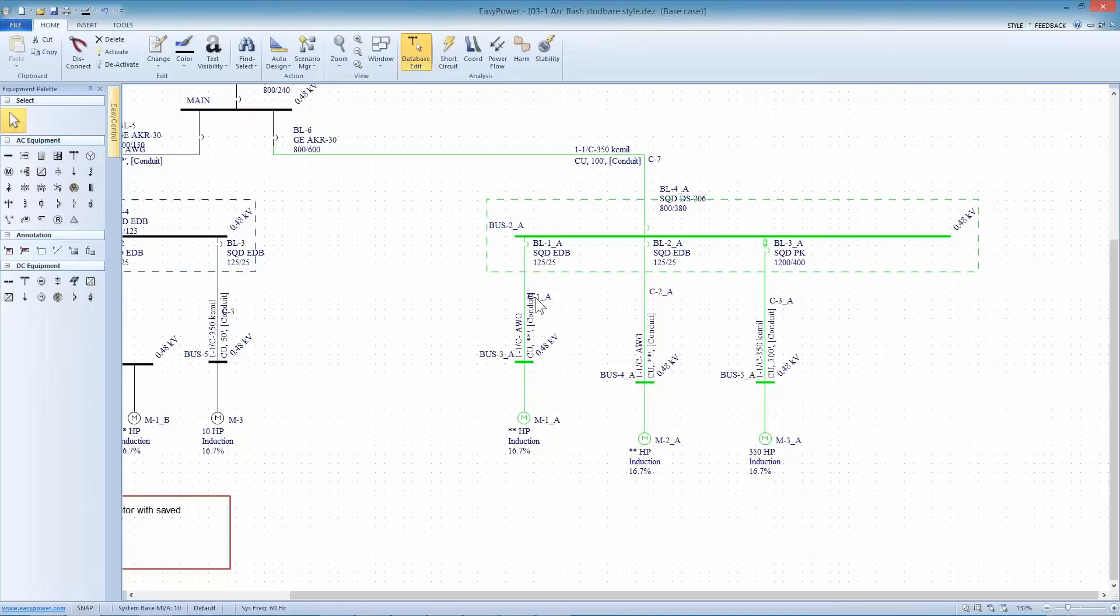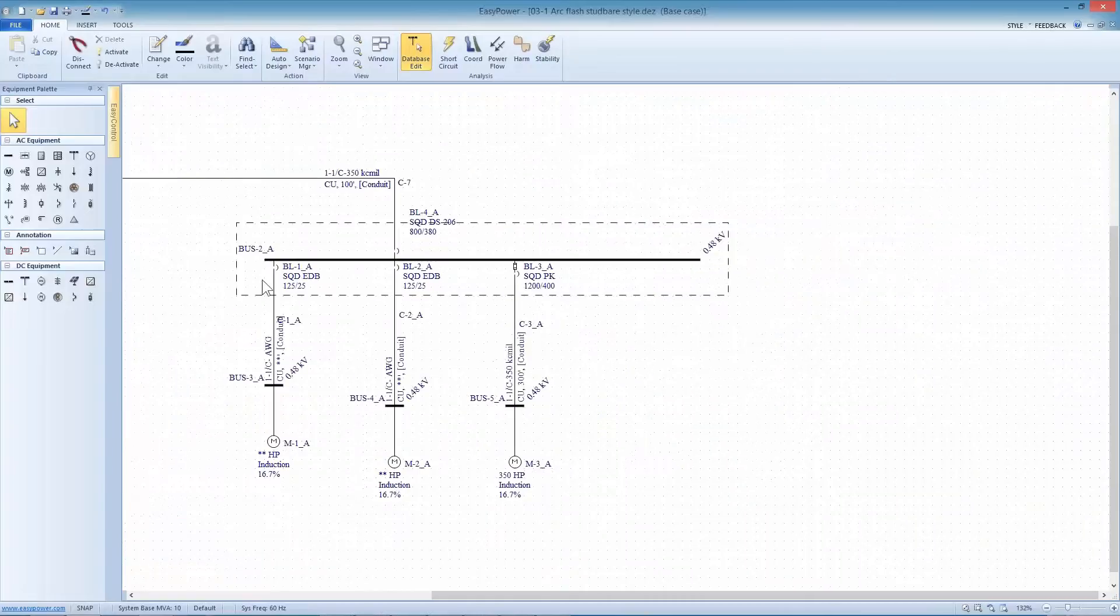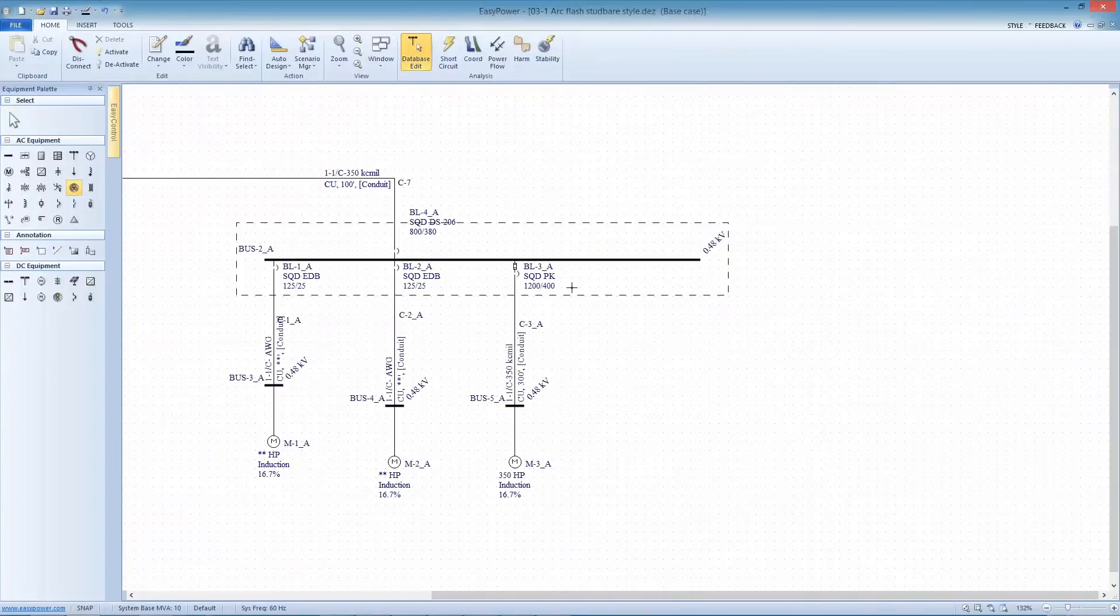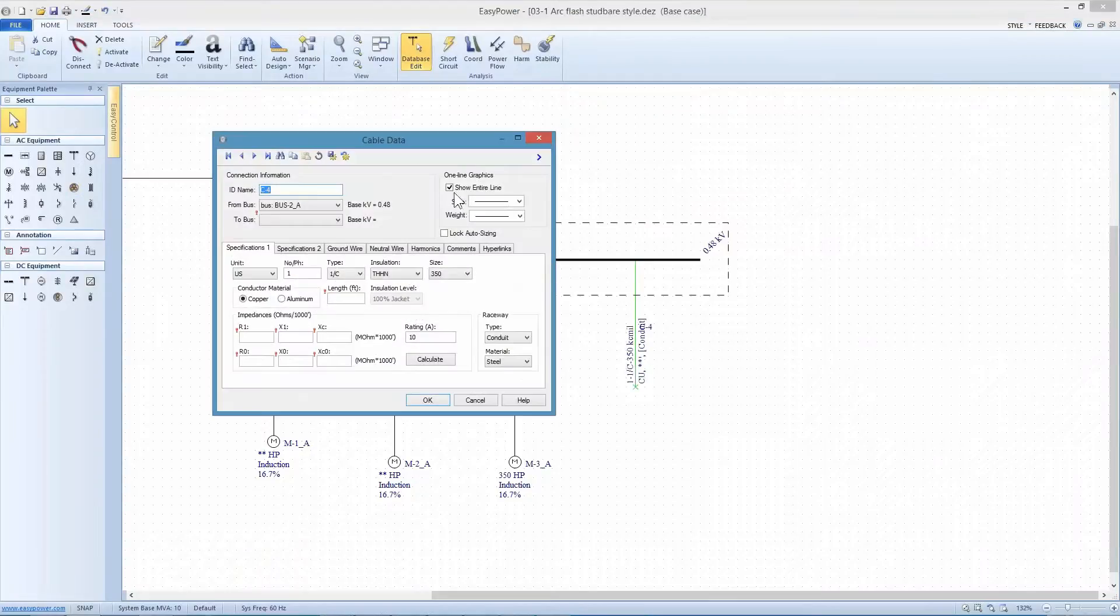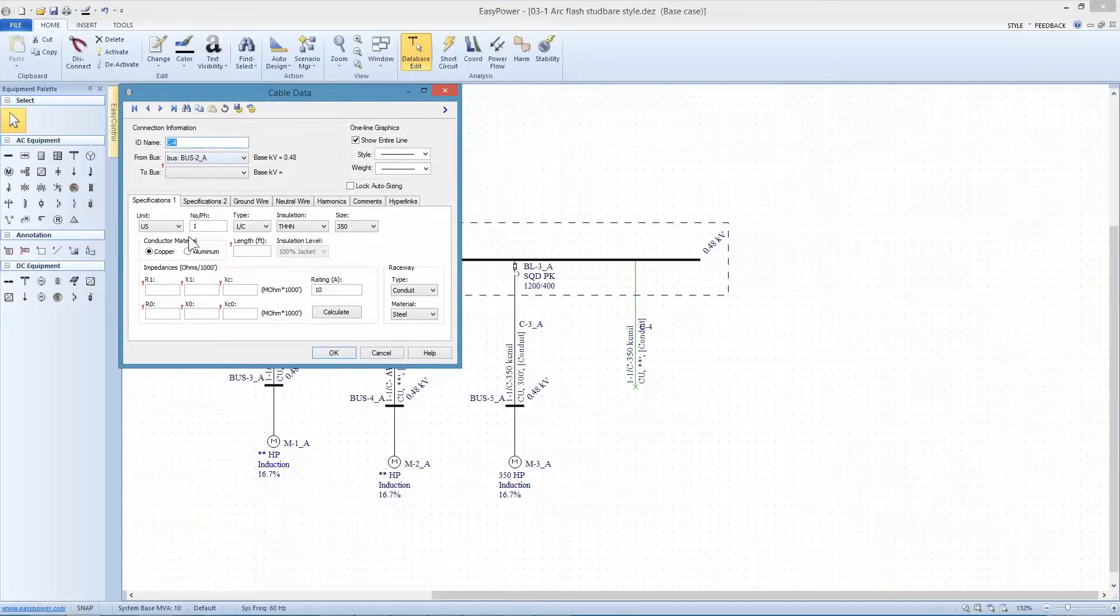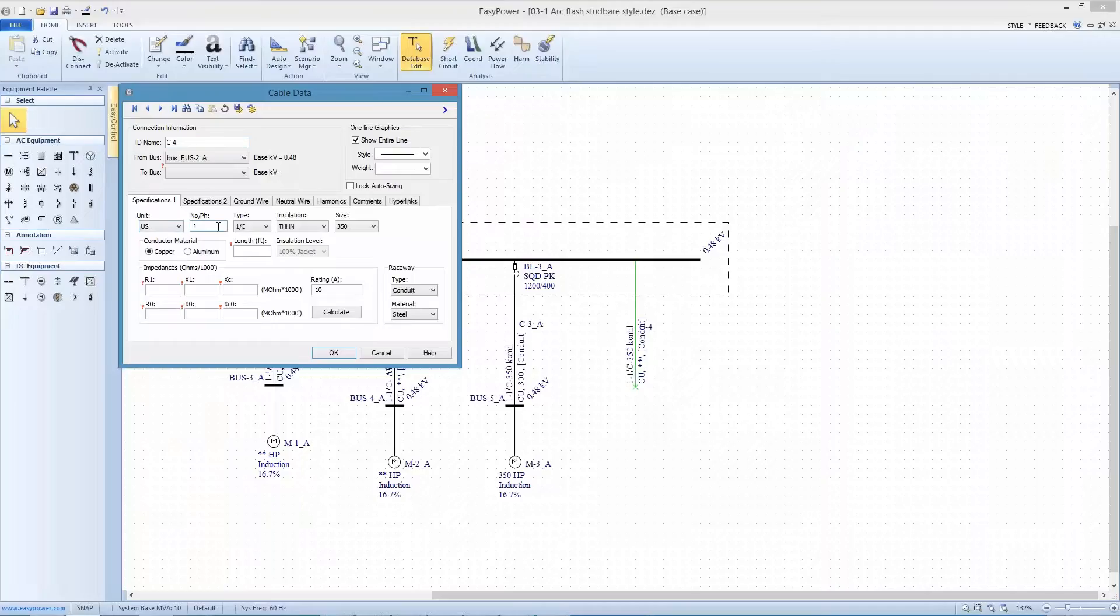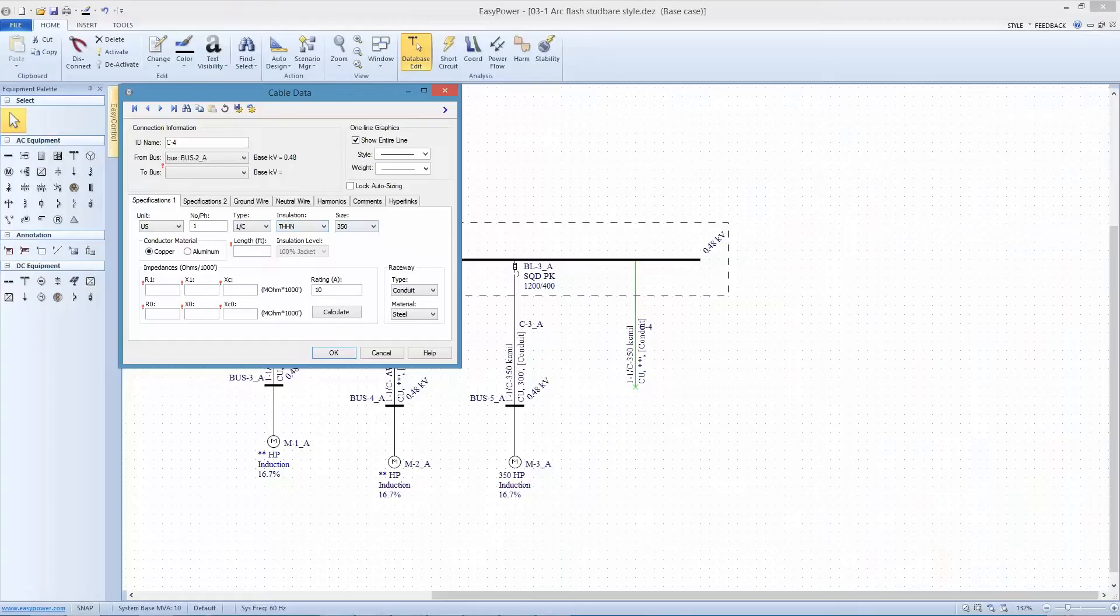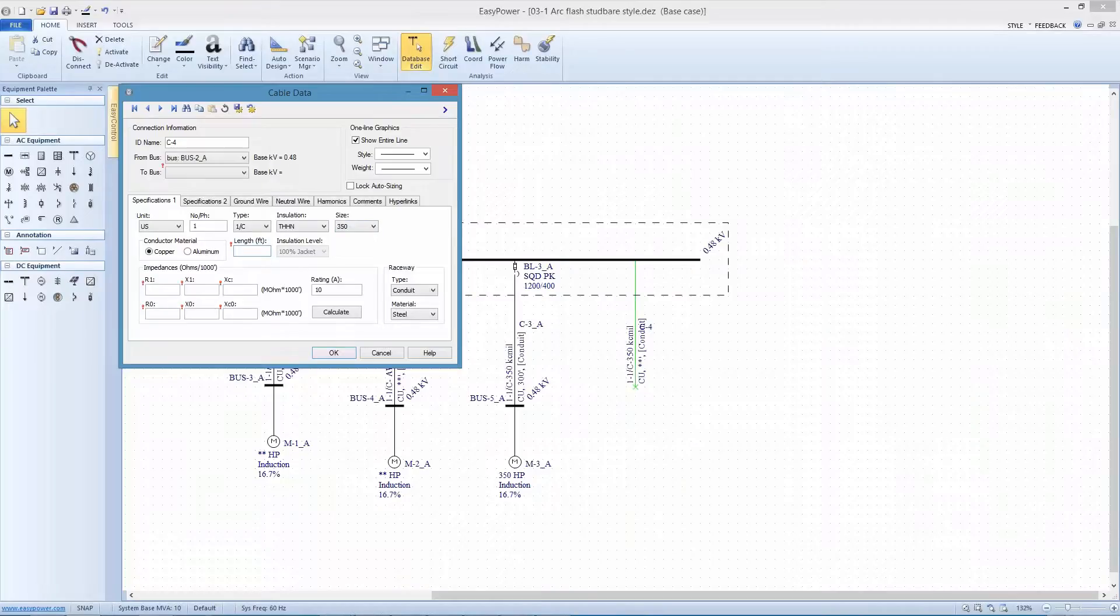Let's go back to my one-line diagram. I'll put a spare cable in and look at how the tool deals with the data. As I enter a cable and open up the Cable Data dialog box, I can see there's some amount of data already put in here, and then some that has red exclamation points that I need to enter. Once I've told it which units we're using, the number of conductors per phase, the type of cable which is single core, the type of insulation, and the size, the only other element I need to enter is the length, and it will calculate the rest of these elements for me.